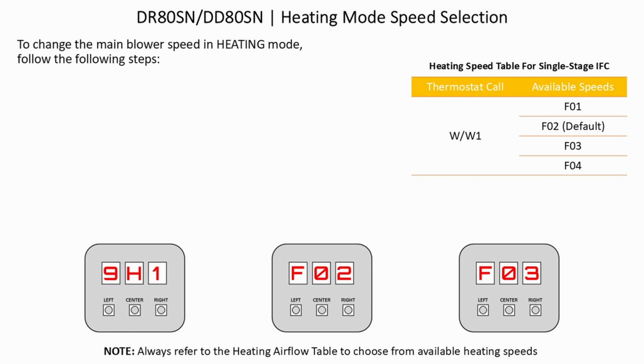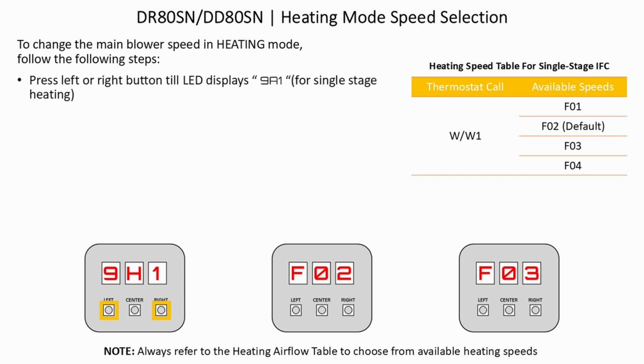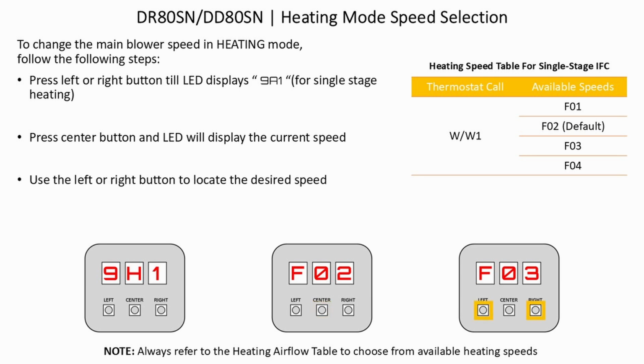To change the main blower speed in heating mode, follow these steps. Press the left or right button until the LED displays GA1 for single-stage gas heat. Press the center button and the LED will display the current speed. Use the left or right buttons to locate the desired speed. Press the center button to select the desired speed. Note: always refer to the heating flow table and choose from the available heating speeds.